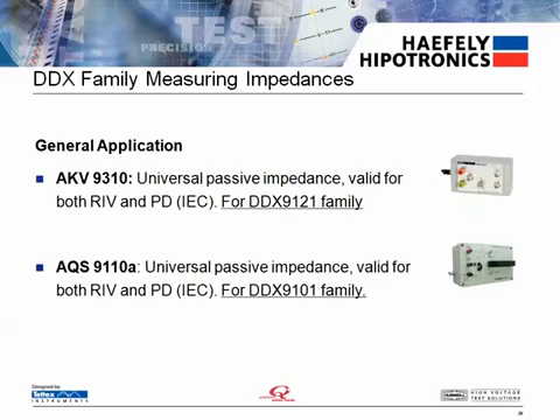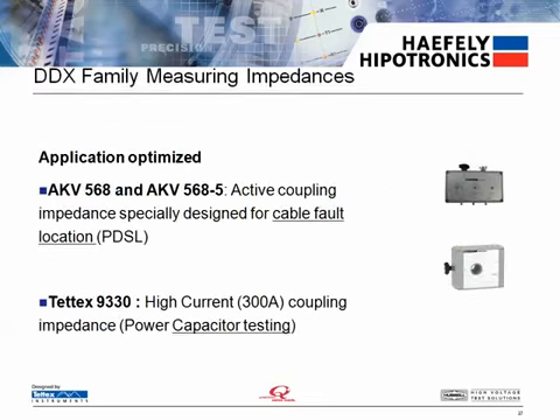If a user has an existing coupling capacitor, they can replace its low arm with one of our universal passive measuring impedances for easy upgrades to one of our DDX PD detectors. The AKV 9310 is optimized for the DDX 9121B, and the AQS 9110A is optimized for the DDX 9101. We can also offer measuring impedances for specific applications such as fault site location cable testing and power capacitor testing.